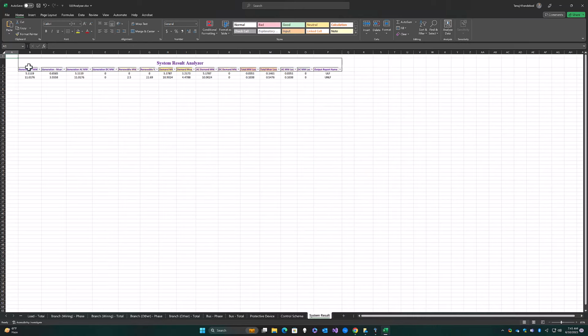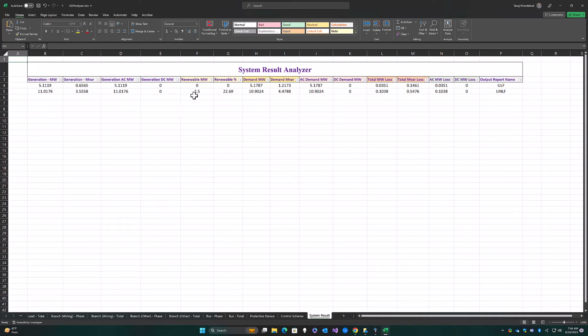And you can also see a final summary of the total system demand and generation across different scenarios, and you can see how the losses vary from one scenario to another. So again, it's a very typical load flow result analyzer, but this one is unique in the sense that it's comparing each phase with respect to each other. And it's also able to compare the low voltage pickup settings with respect to the alert settings that you have for your unbalanced load flow. So it will let you know if your protected device will trip on long time, not just based on the frame rating of the breaker. So this is the unbalanced load flow result analyzer in ETAP 2023.